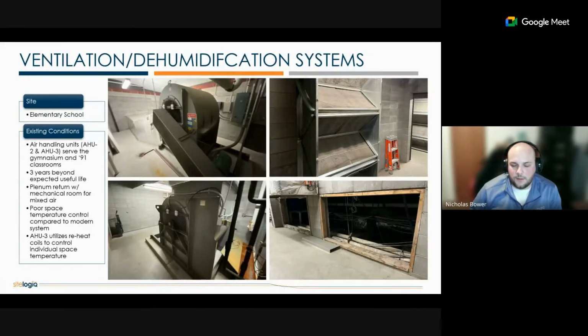They serve the 91 classrooms and the gym, and are 3 years beyond their expected useful life. In the bottom right corner is the type of return system that brings air back from the spaces, a plenum return. These units use an older style of technology, so they provide poor space temperature control compared to newer modern systems. Air handling unit 3 utilizes reheat coils to control individual space temperature, which doesn't really allow you to modulate airflow into the spaces; it just helps with heating them.